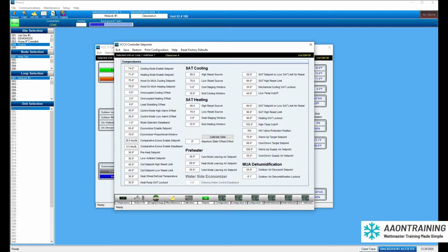Space sensors in AAON units are the most common form of control sensor, but you could take a makeup air unit, for example, and that would require an outside air sensor, because the space sensor or supply sensor or whatnot just simply wouldn't be able to change temperature and figure out exactly what's going on with the temperature fast enough. So you need something that's outside in the airstream, ready to change it to heating, cooling, or vent mode at the drop of a hat.